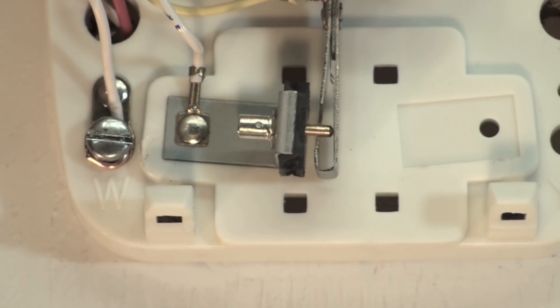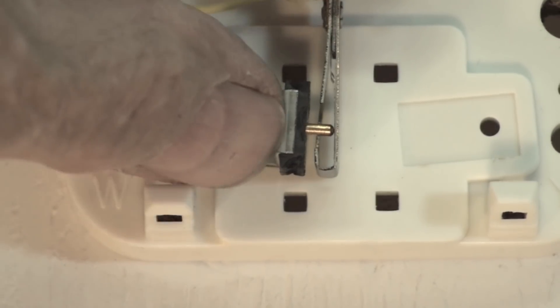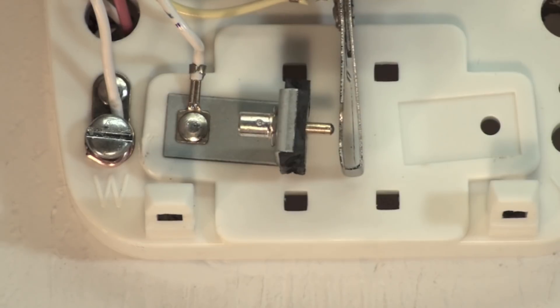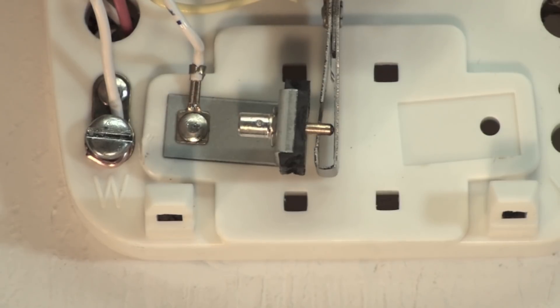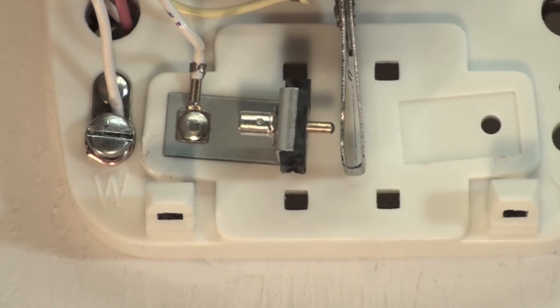Not a lot of power going through it but they still will arc. So there's a magnet right here, and when this bimetal gets close the magnetism pulls it towards it. Then as the bimetal starts to move the other way it just pops loose like that. I'm going to show you how the bimetals work on these two.